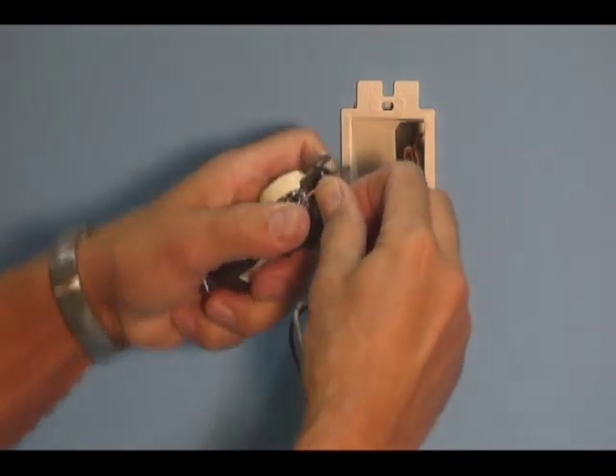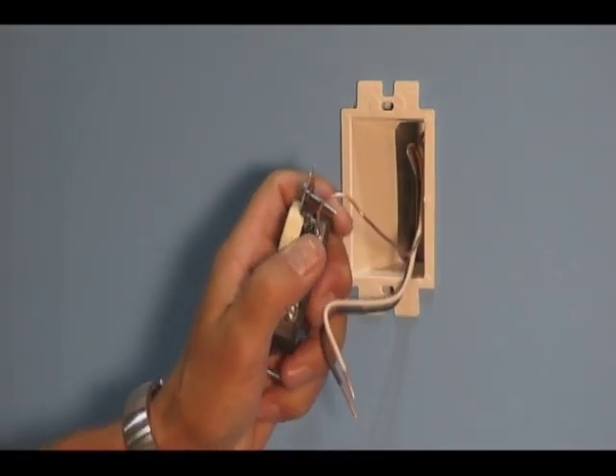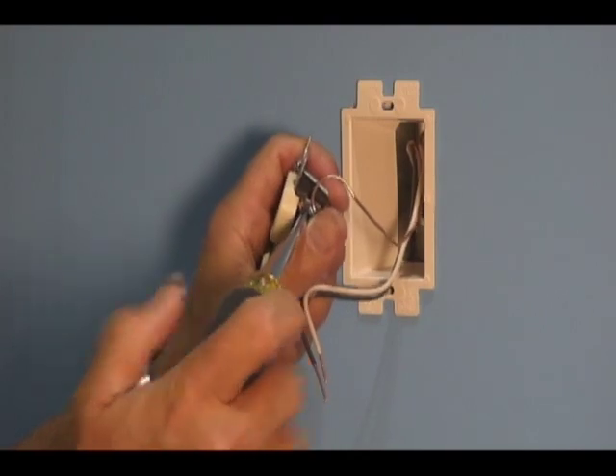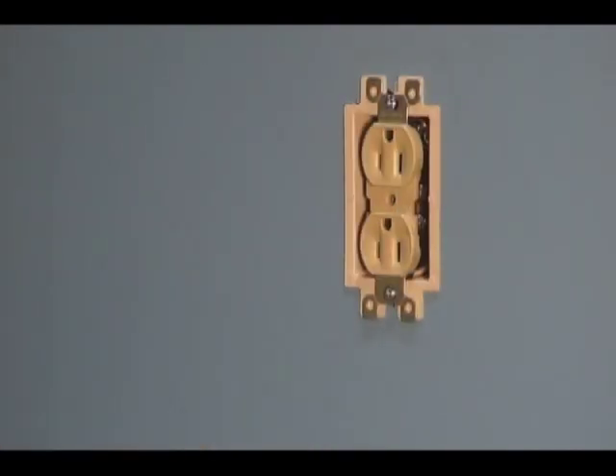That is, a box that's set back no more than a quarter inch in a non-combustible wall, and one with no setback in a combustible wall.